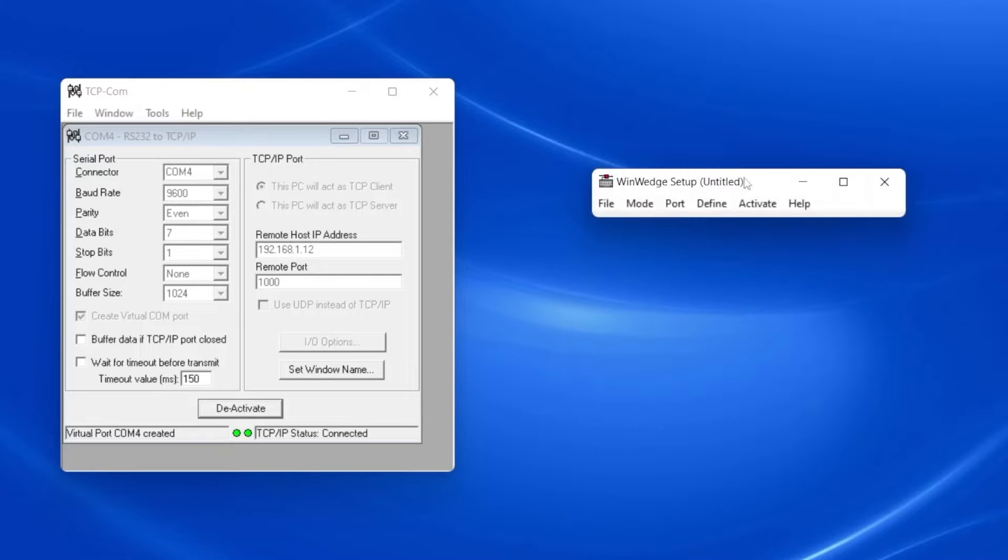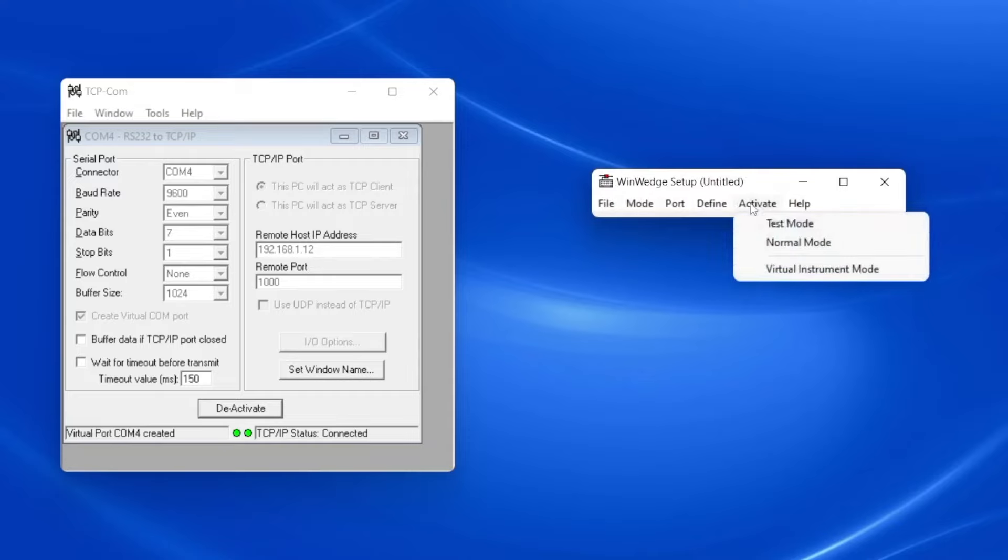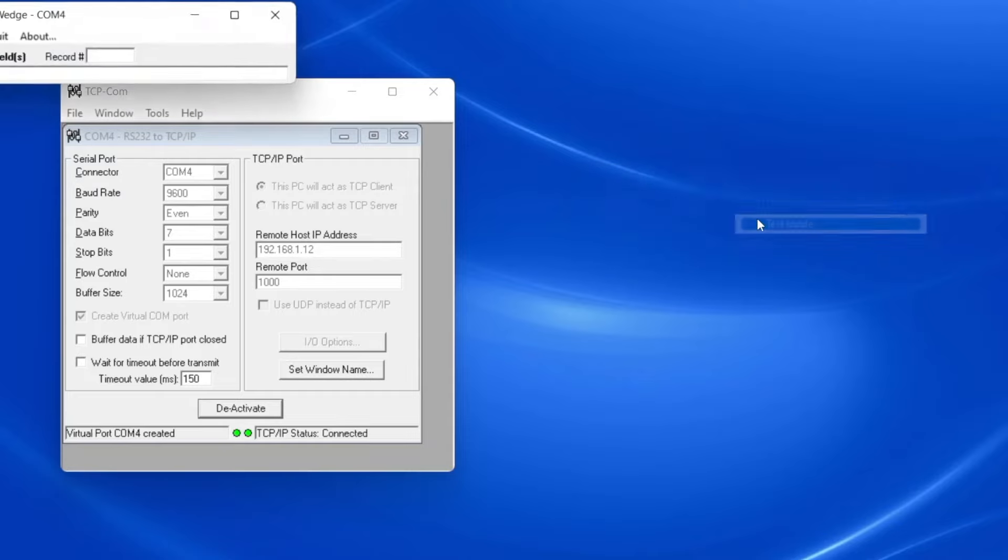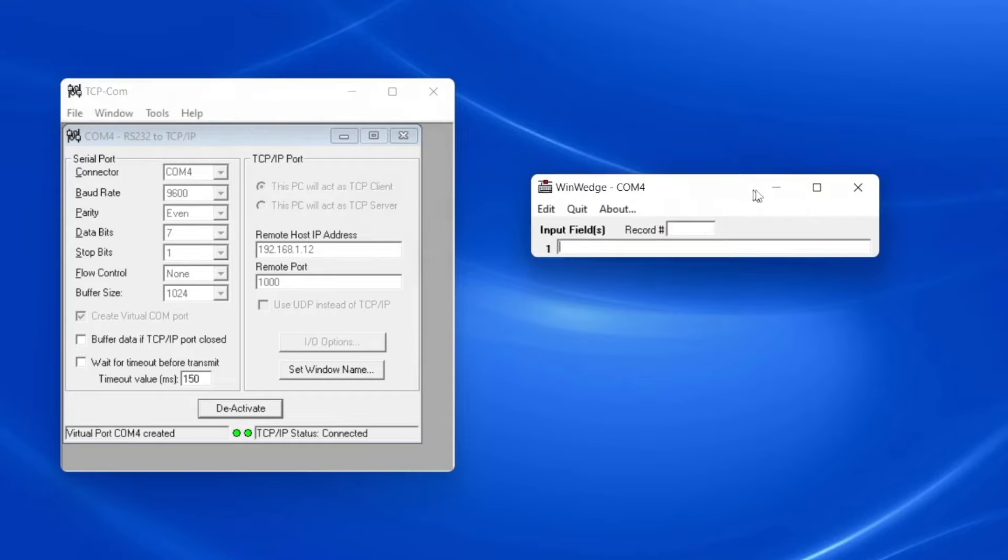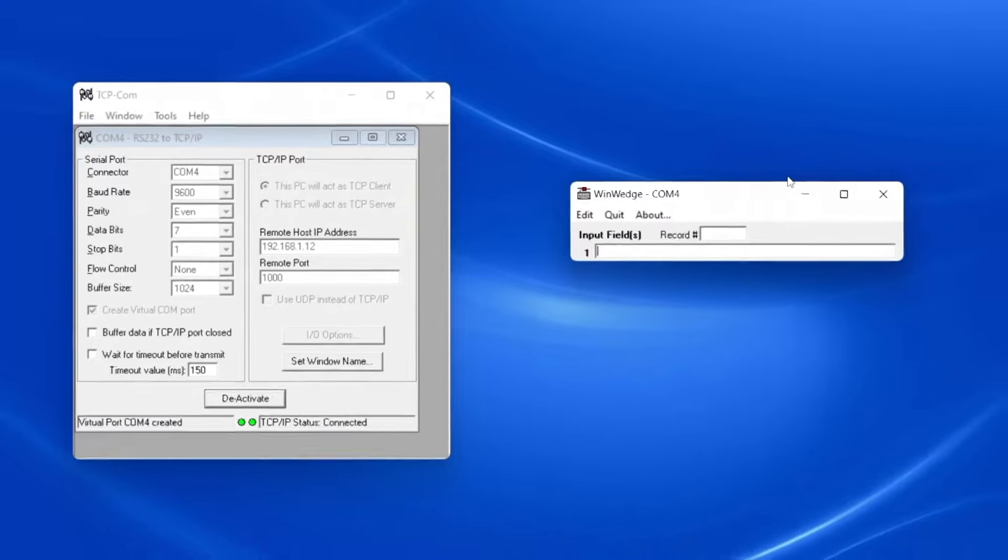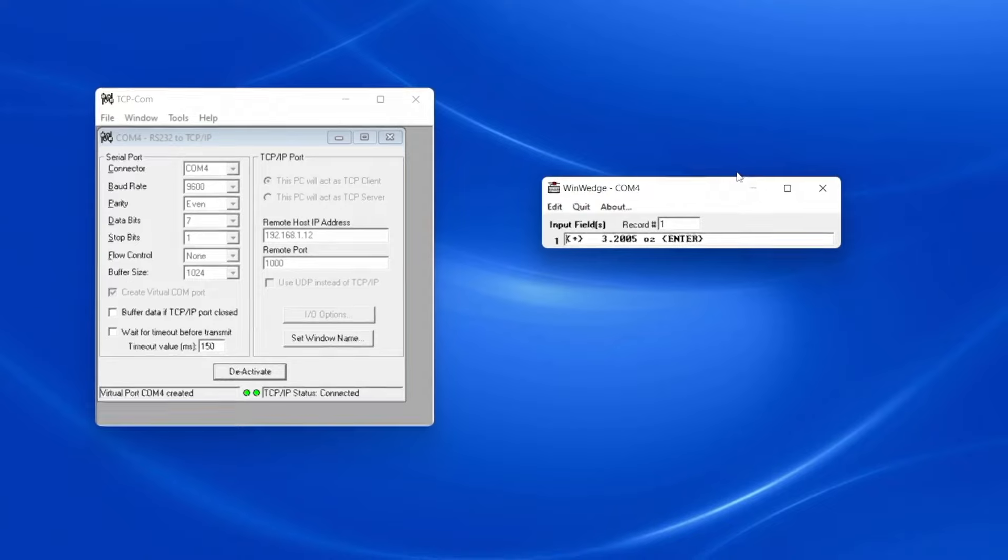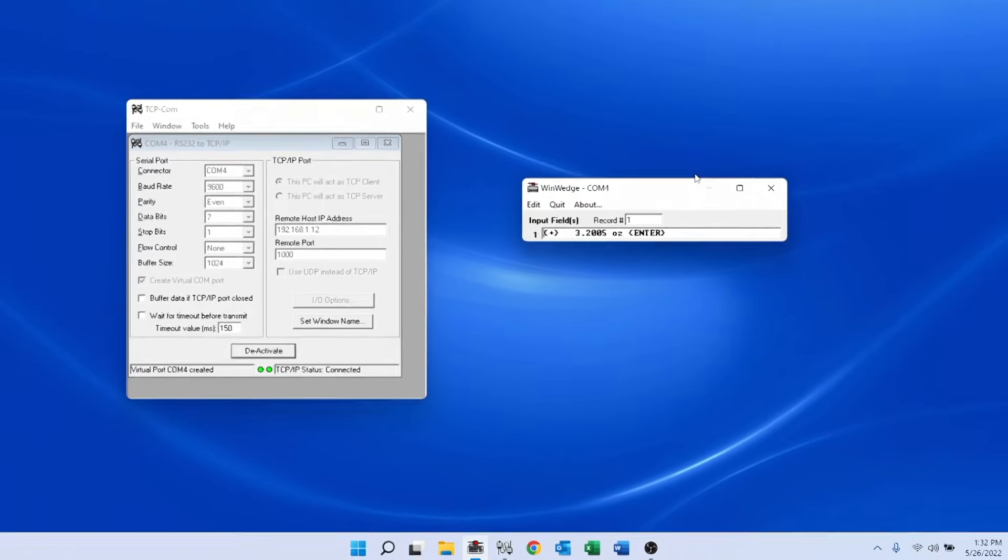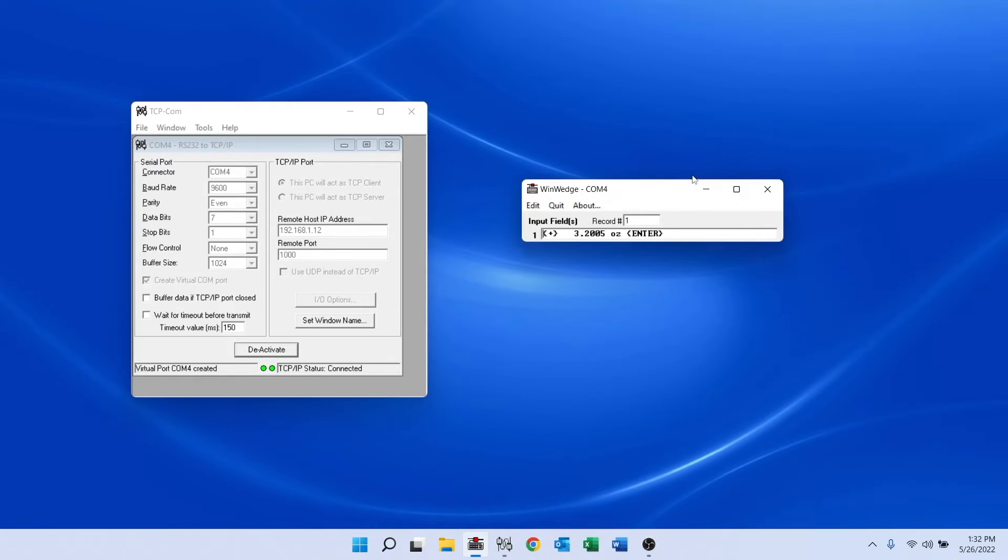WinWedge lets me test that I'm able to receive data in its Analyze window. When I press the print button on my balance, I can see that the weight data sent over the network is being received by WinWedge exactly as if it were being received using a legacy, physically connected RS-232 COM port.